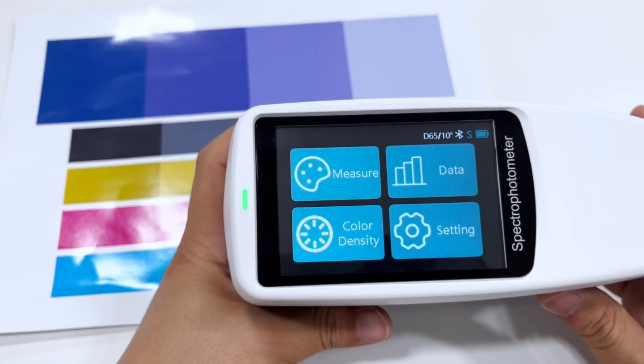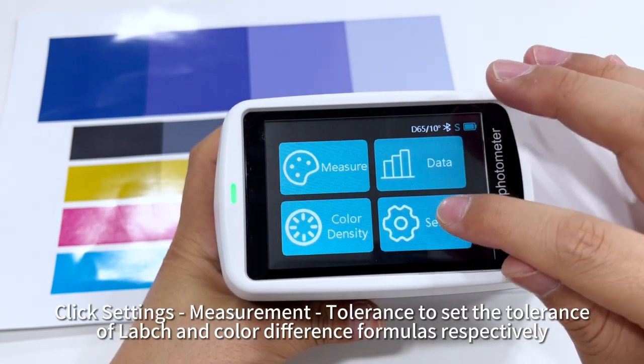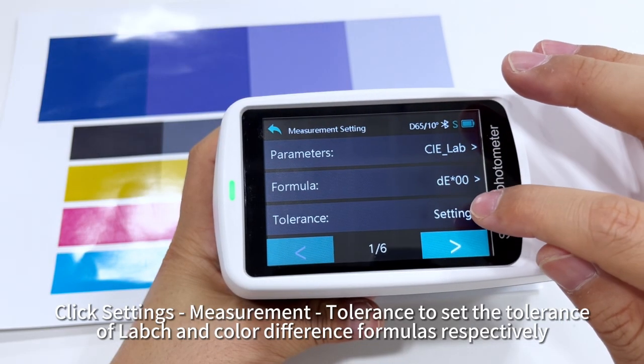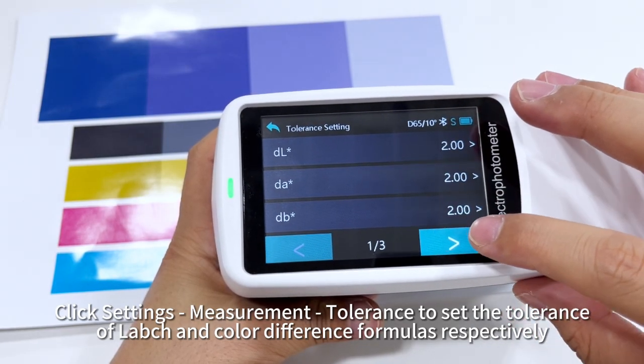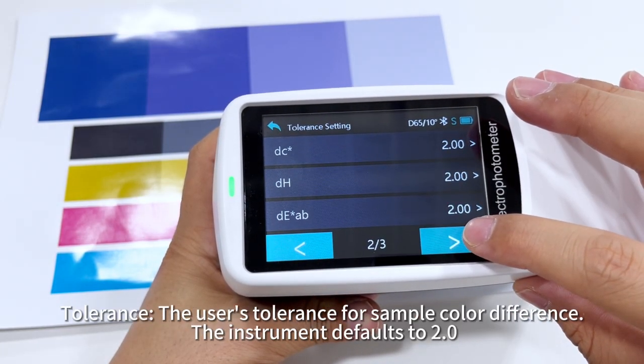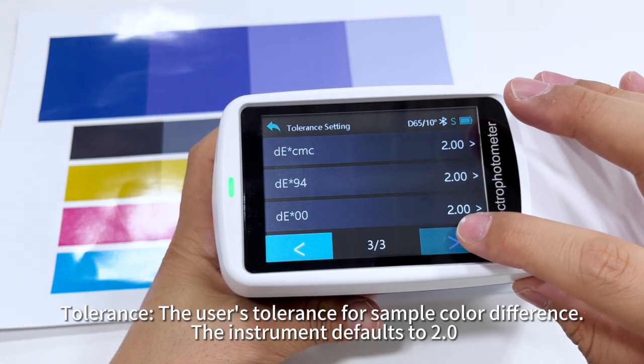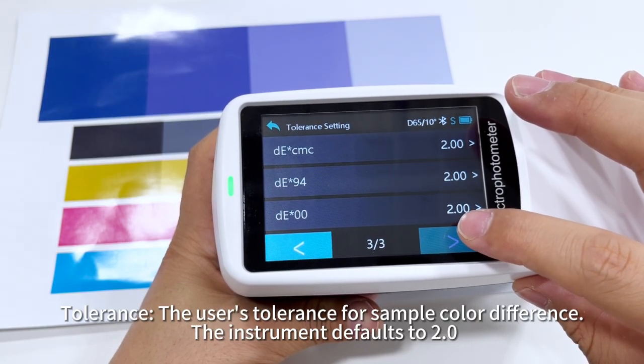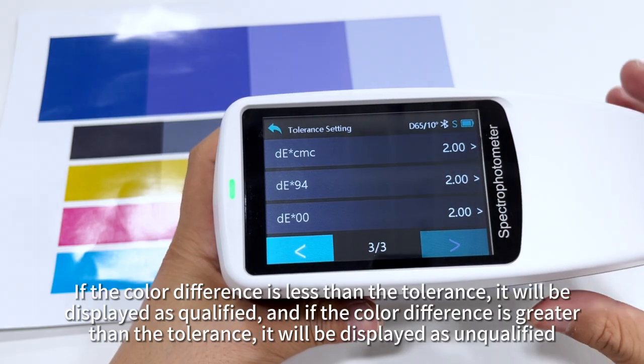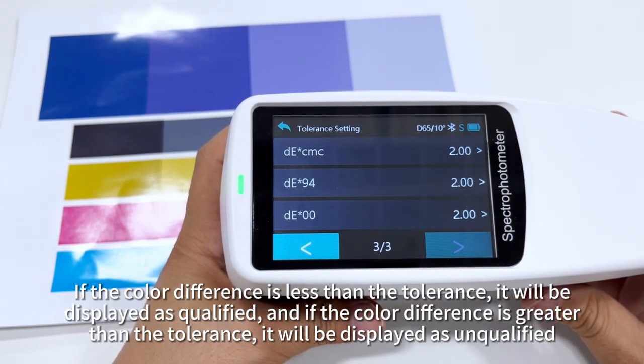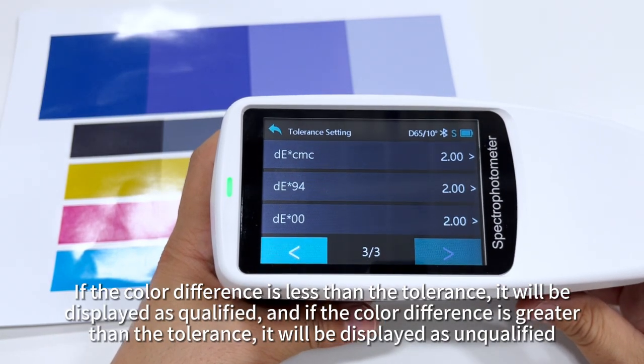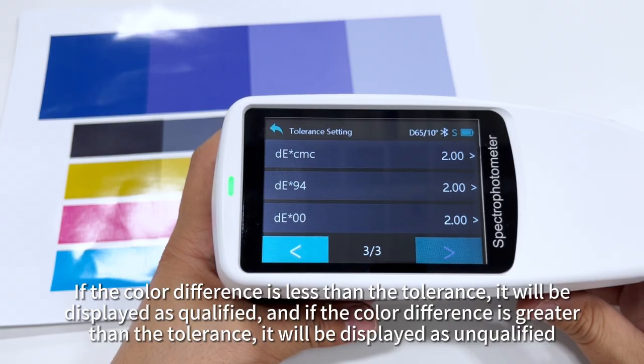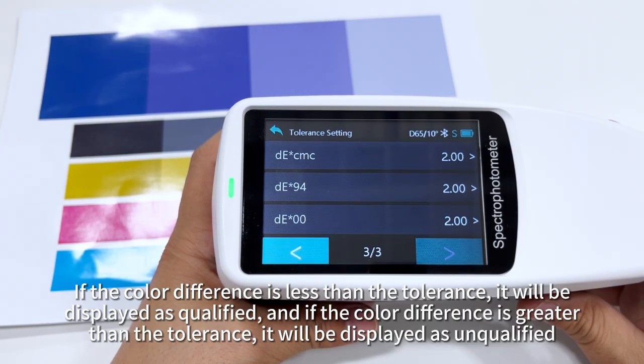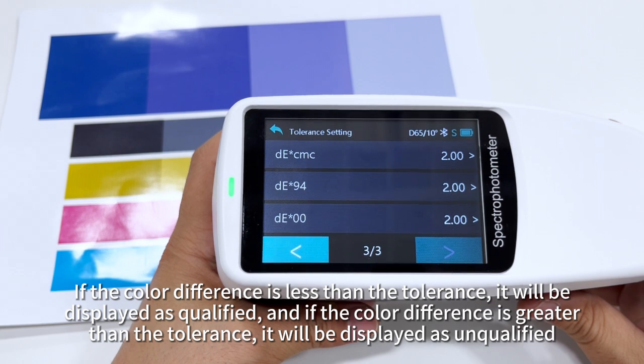Tolerance settings. Click Settings, Measurement, Tolerance to set the tolerance of LABCH and color difference formulas respectively. Tolerance is the user's tolerance for sample color difference. The instrument defaults to 2.0. If the color difference is less than the tolerance, it will be displayed as qualified, and if the color difference is greater than the tolerance, it will be displayed as unqualified.